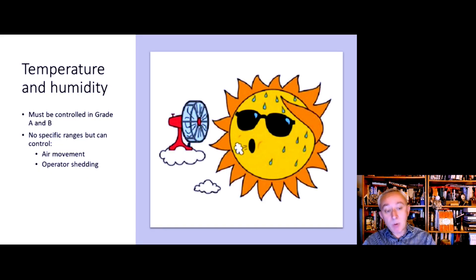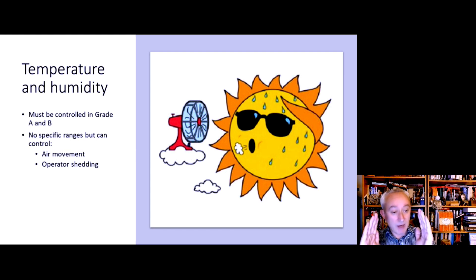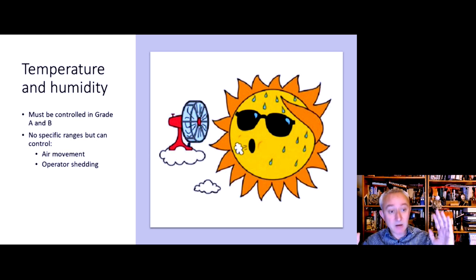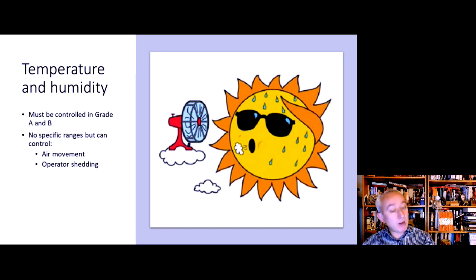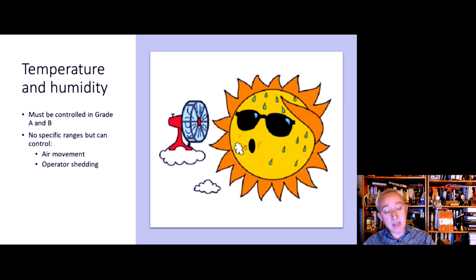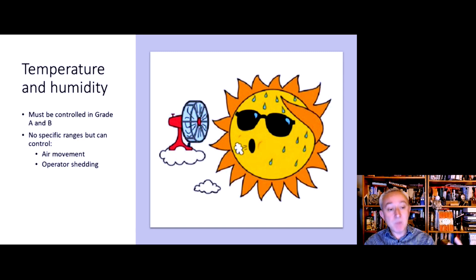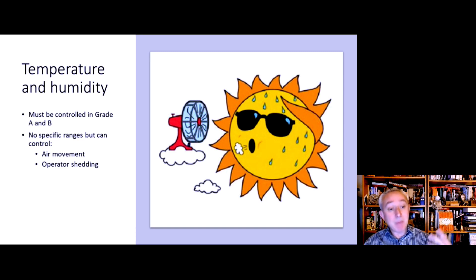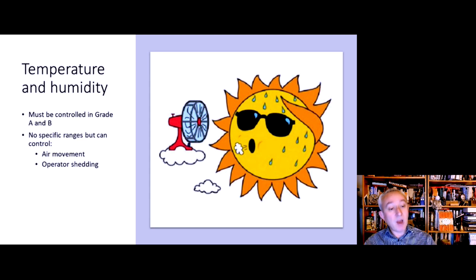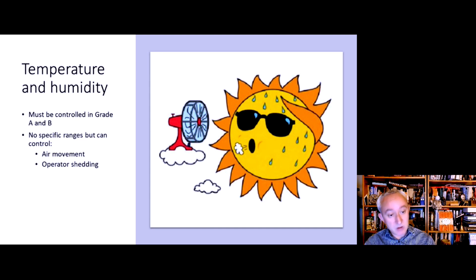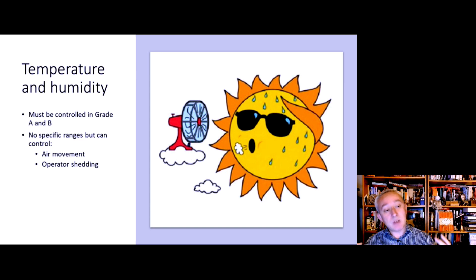It's also important that temperature and humidity are controlled and considered. These must be controlled for grade A and for grade B. Now, there are no specific ranges described in the revised Annex, but these need to be appropriate and defined by the contamination control strategy, because variations in temperature and humidity can impact upon air movement. Also, they're important for operator comfort, and if operators get too hot or too sweaty, then the ability of the clean room suit to contain contamination is going to be compromised.